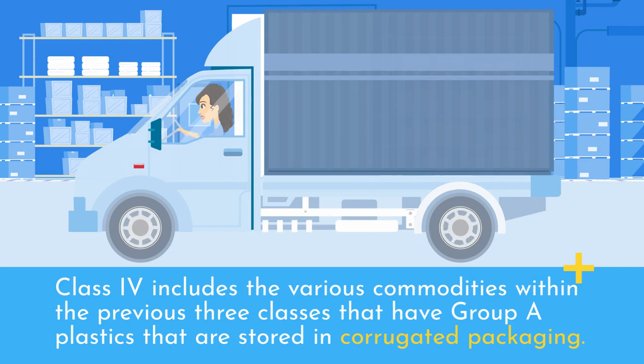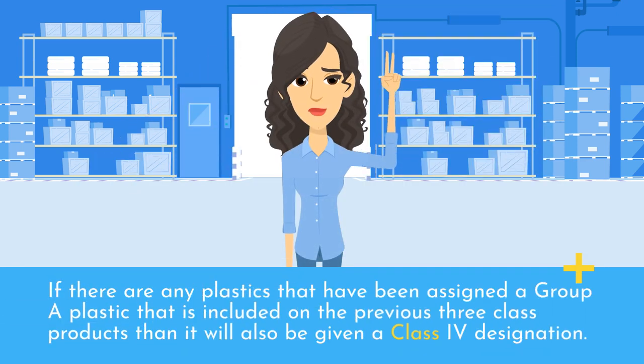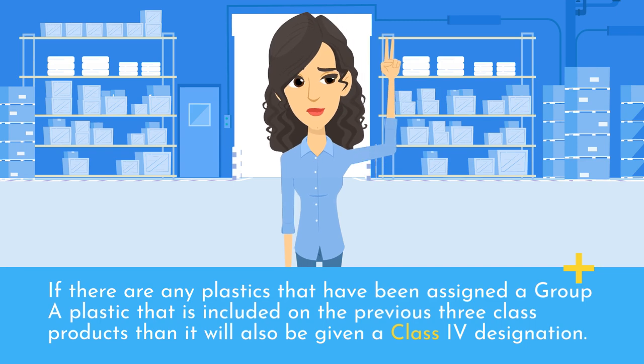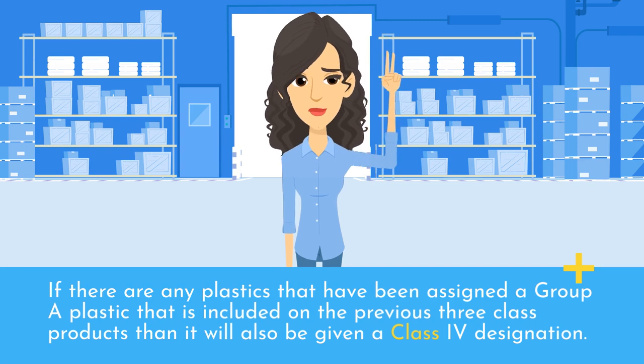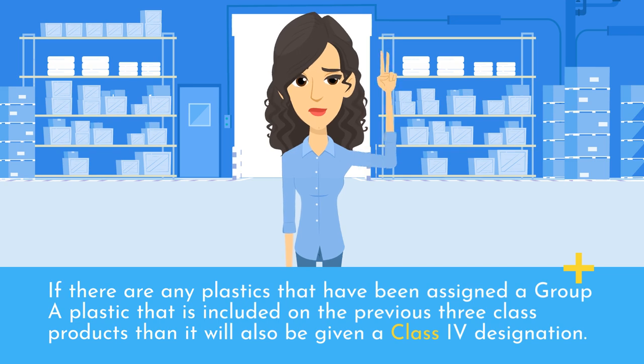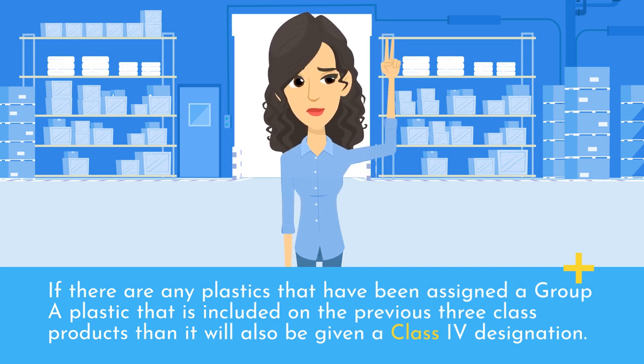Class IV includes the various commodities within the previous three classes that have Group A plastics stored in corrugated packaging. If any plastics assigned a Group A classification are included on previous three class products, then it will also be given a Class IV designation.